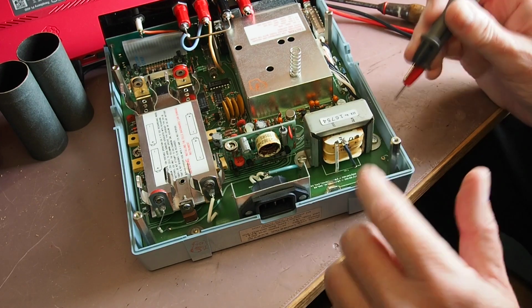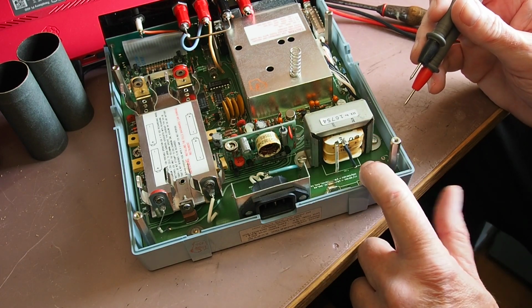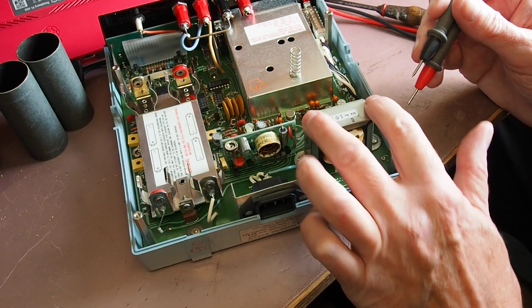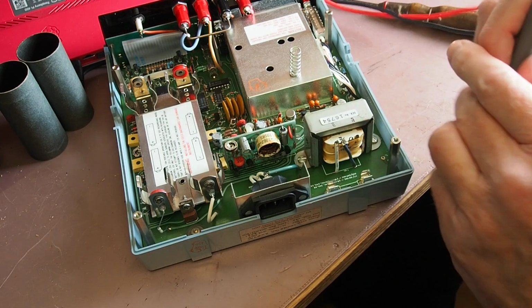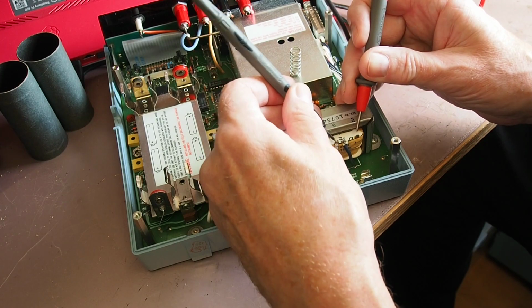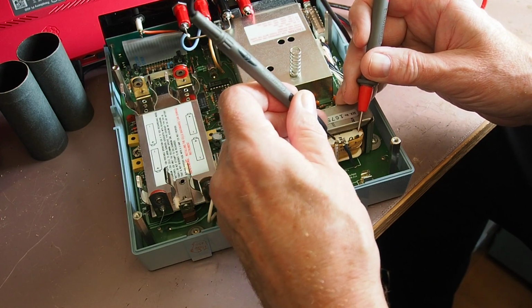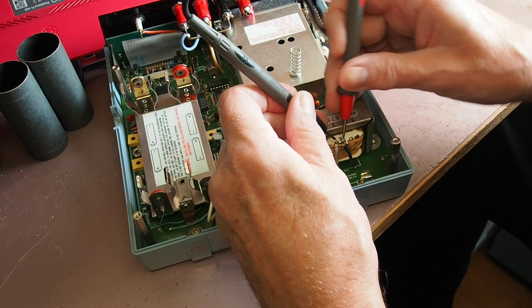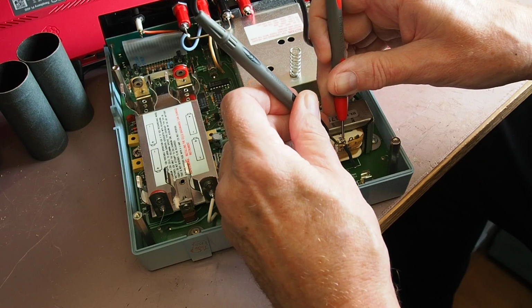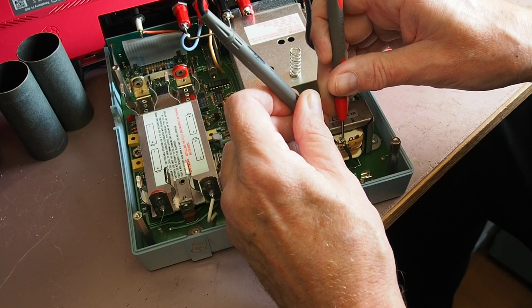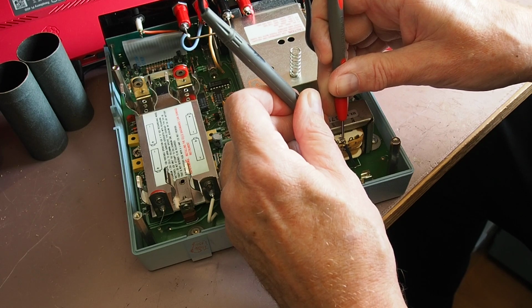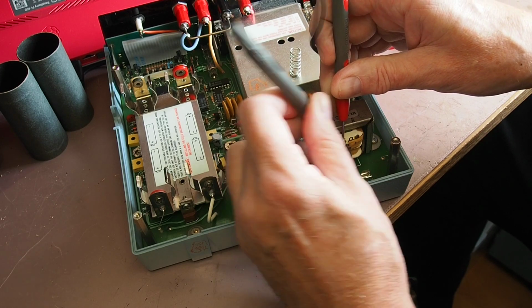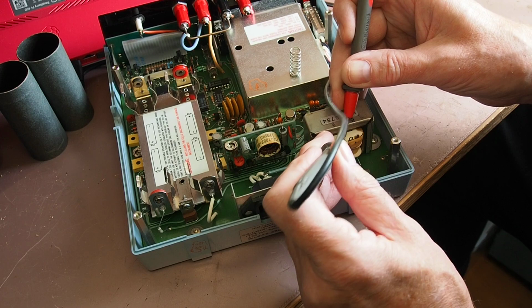So if that fuse did its job and protected the transformer, we should get resistance across those 2 terminals. I'm going to put the probes on there as best I can, and it's telling me 116 ohms. That's very good news.